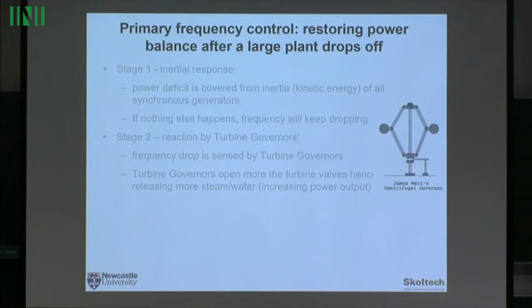But what will happen is that all the generators have those turbine governors, which James Watt actually came up with first. Now they're electronic rather than mechanical, but the principle is the same. That point moves up and down depending on the speed of rotation. If the speed of rotation drops, that point moves and opens turbine valves, so more steam comes through, meaning more power is generated, and the whole thing continues until balance is reached.